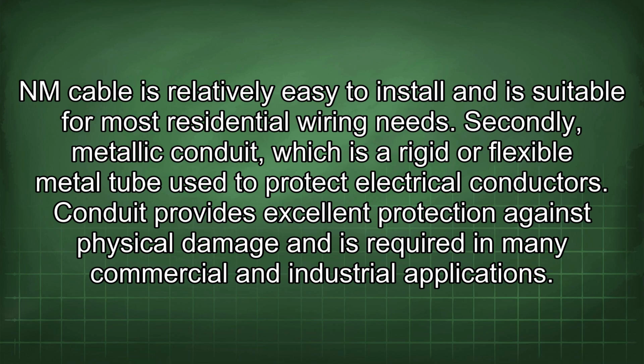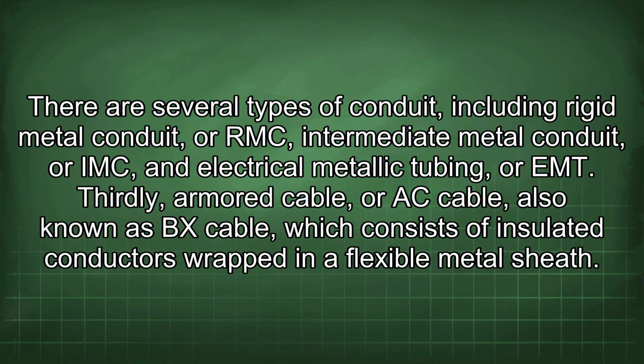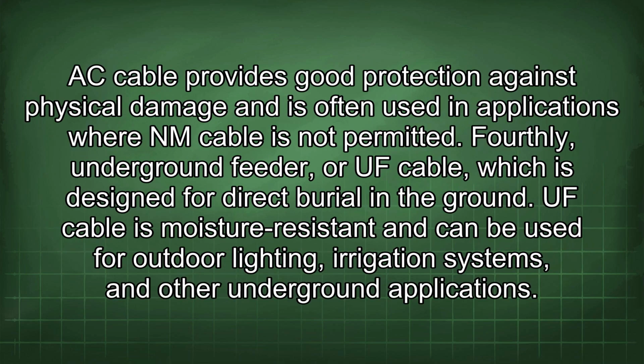NM cable is relatively easy to install and is suitable for most residential wiring needs. Secondly, metallic conduit, which is a rigid or flexible metal tube used to protect electrical conductors. Conduit provides excellent protection against physical damage and is required in many commercial and industrial applications. There are several types of conduit, including rigid metal conduit, or RMC, intermediate metal conduit, or IMC, and electrical metallic tubing, or EMT. Thirdly, armored cable, or AC cable, also known as BX cable, which consists of insulated conductors wrapped in a flexible metal sheath.